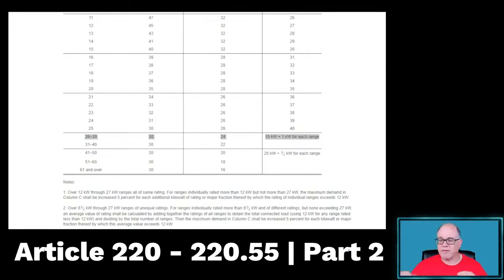And the first thing somebody will say is, Paul, why would you start off with one that's so freaking complicated? It's not complicated. What does column C say to do for 30 12 kW ranges? Remember, it's not over 12. It's 30. So I am in column C. So let's go back to the presentation and we'll work this thing out.